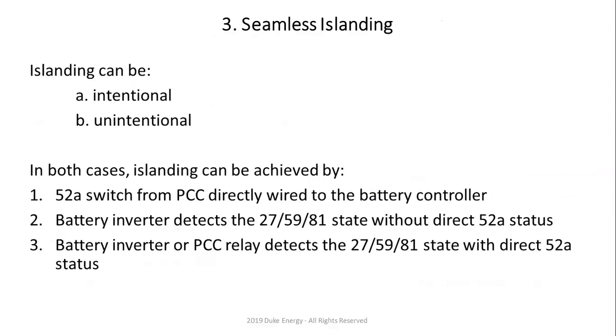So we have done islanding three ways. First of all, we wired the 52A switch, which is the status switch of the PCC, directly to the battery controller. Why? Because the battery is the main source of voltage and frequency from the inverter-based distributed energy resources. Also, you can do that with the microturbine, but the microturbine is slightly different from the implementation standpoint. So our AC-coupled battery is the main source of voltage and frequency when we go into the island. As you wire the 52A switch, you have to transmit that real fast. The 52A switch of the PCC, which is the recloser, you're looking at about 4 to 6 cycles. And when the PCC opens, voltage and frequency changes happen much faster than the status of this switch.